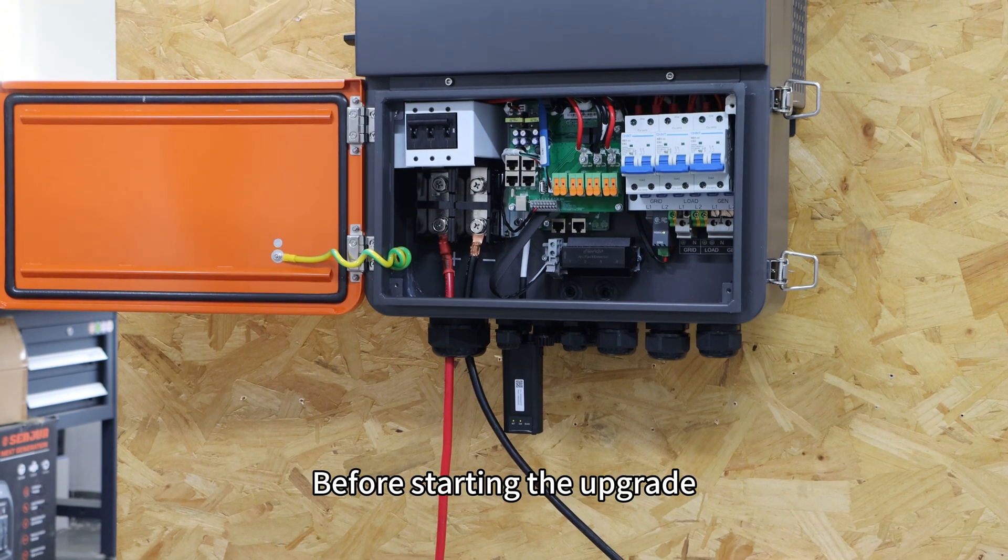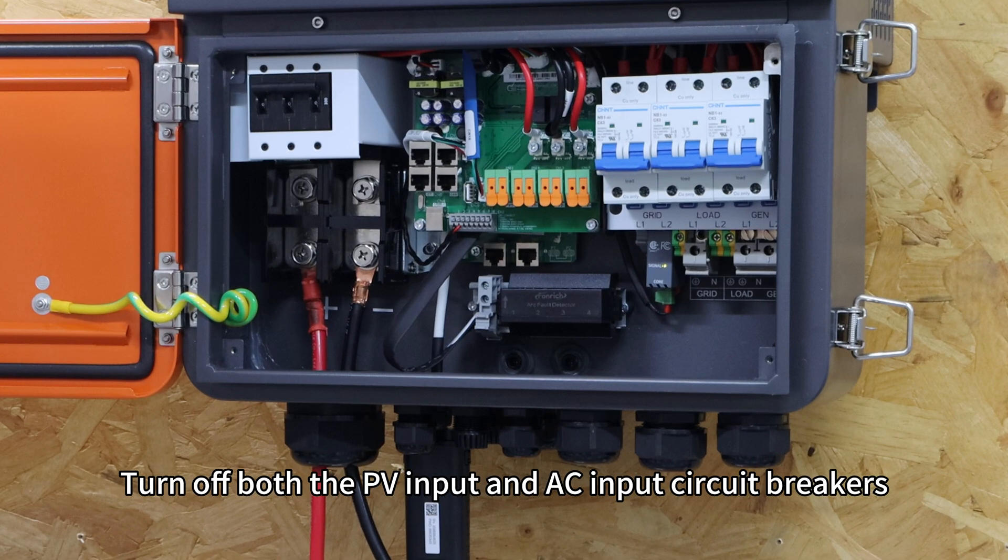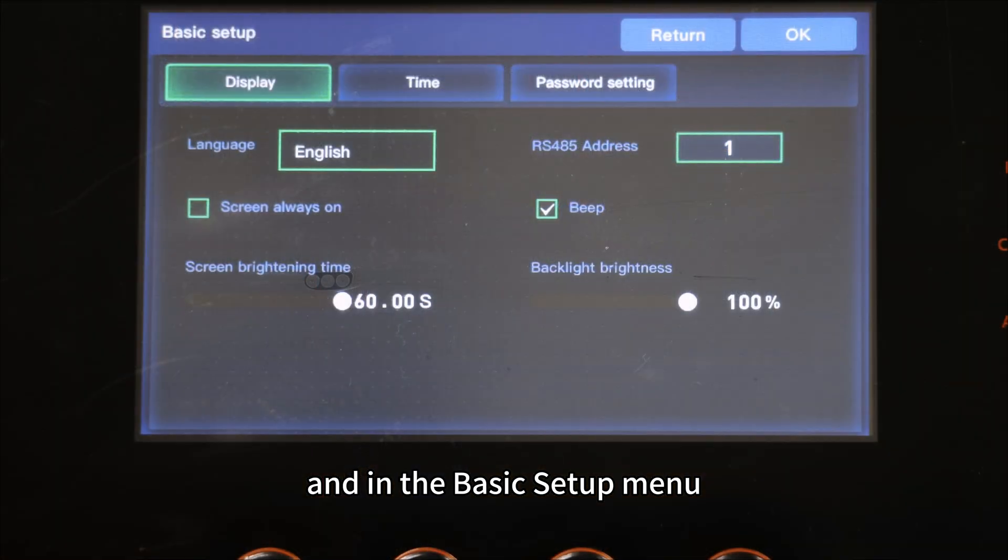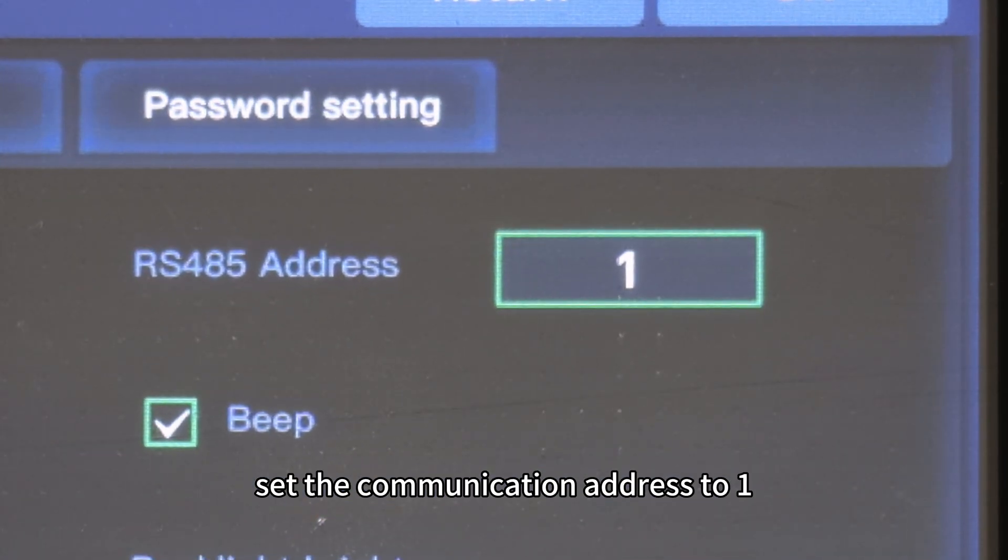Before starting the upgrade, make sure the inverter is not under load. Turn off both the PV input and AC input circuit breakers, and in the basic setup menu, set communication address to 1.